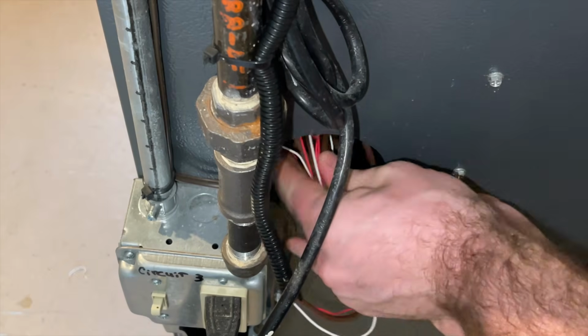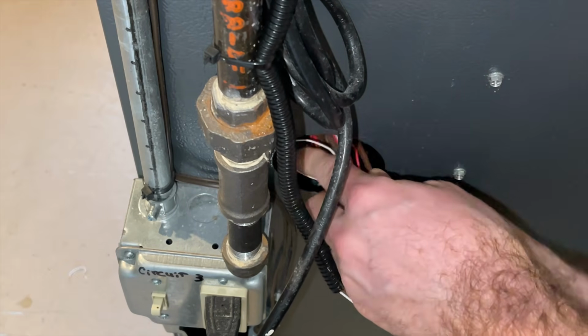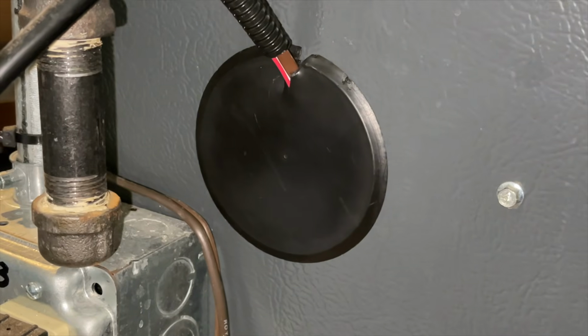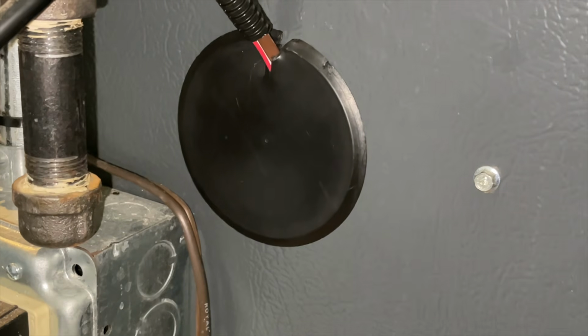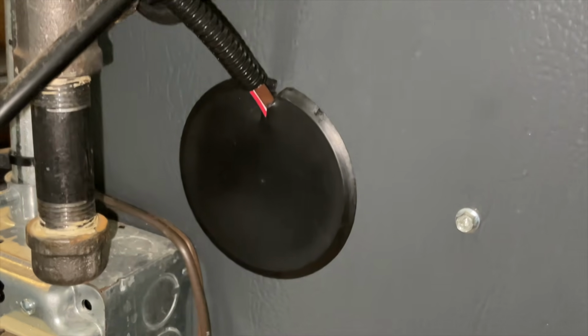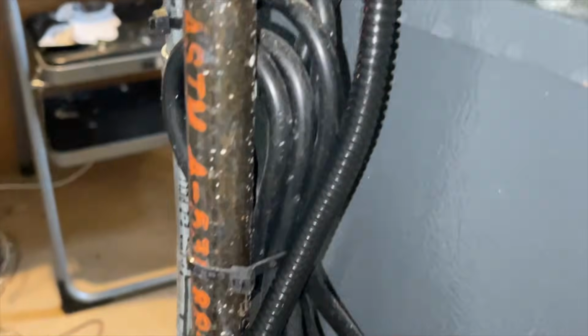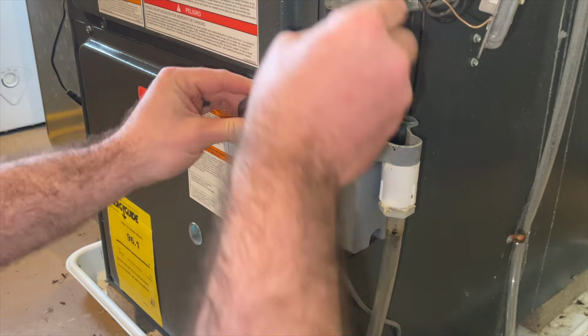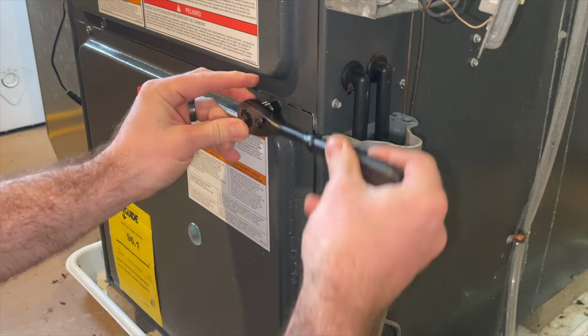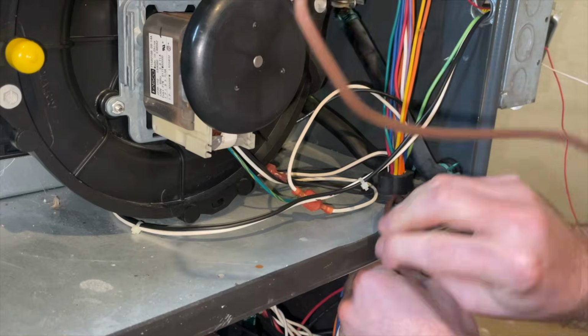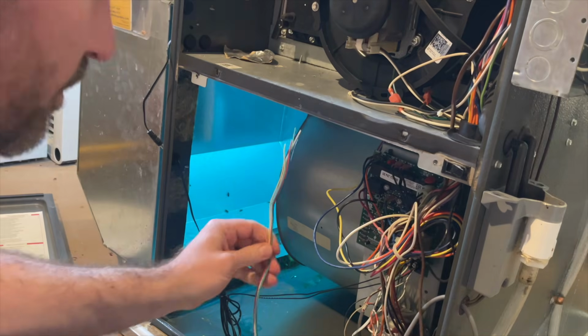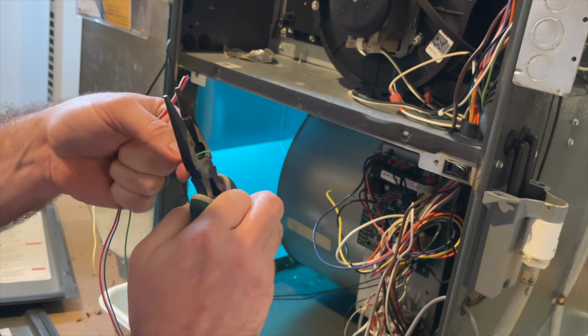All of the cables will split once we get down to the power source, and the 5-wire cable will actually enter the side of the furnace and get hooked up to the main board inside. Now we're going to feed it through, cut it to length, and strip the wires for installation.